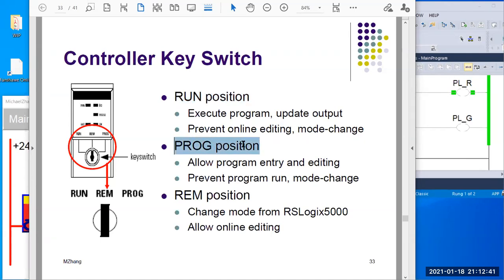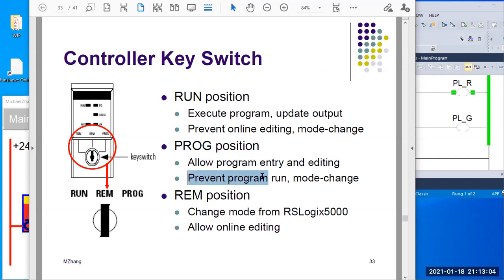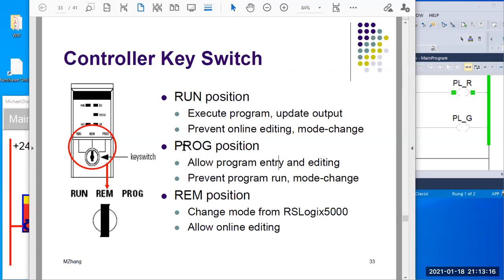The second position I want to talk about is the program position. That will allow program changes with the controller, so you can edit, you can change, you can do anything you want with the program. But at the same time, the program cannot run and the mode cannot change. I don't think I've used this position before. I would assume you can use this in the commissioning phase or debugging — something like that.